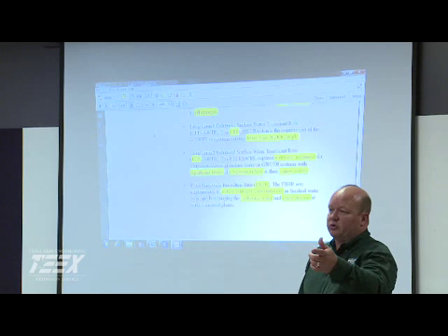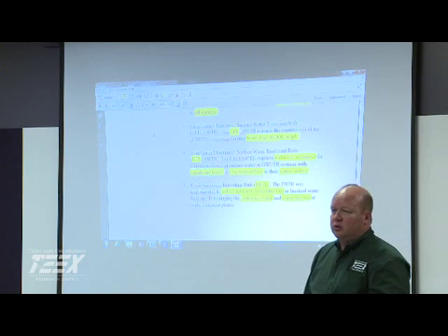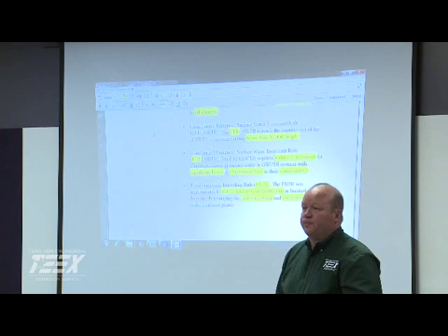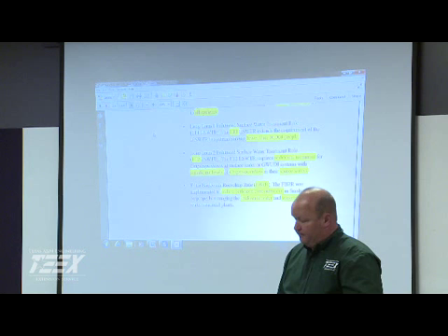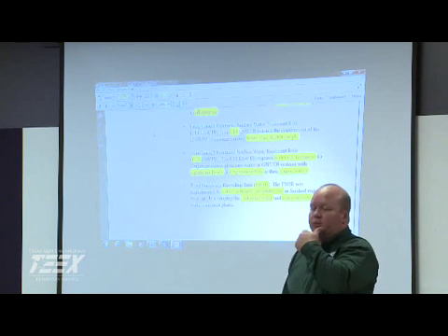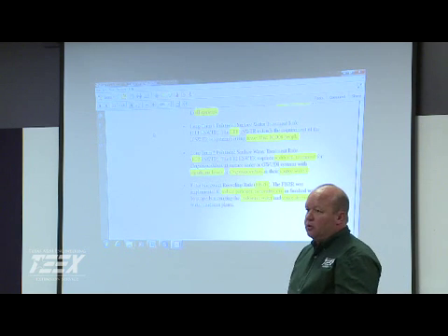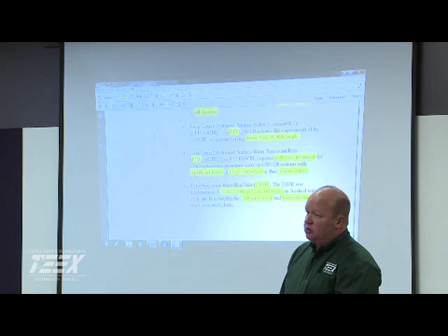Are you doing anything before you discharge? Yeah, we have to put bio tablets in it to dechlorinate it now, simply because they lowered our chlorine limits. We went from like a 1 to 0.04. It's hard because we don't have a long enough time period where we can leave it there long enough. So that's the cheapest way right now, and it's not very cheap, that we found to meet requirements.